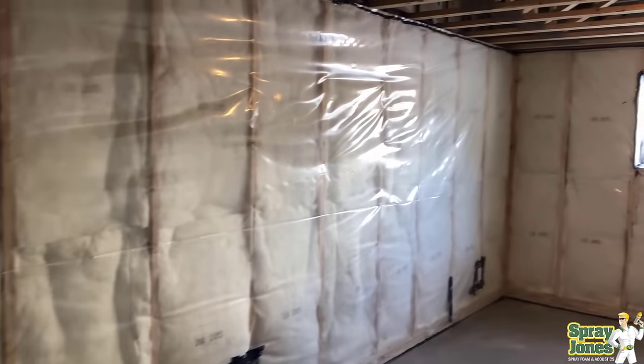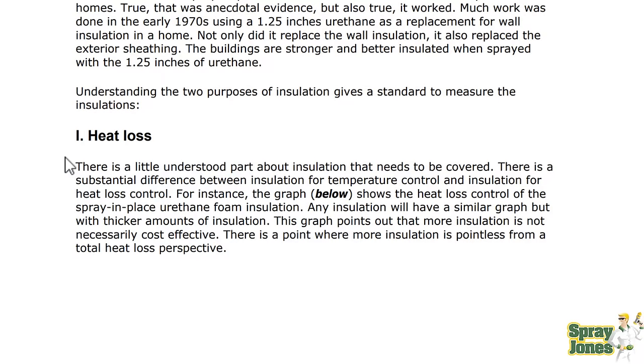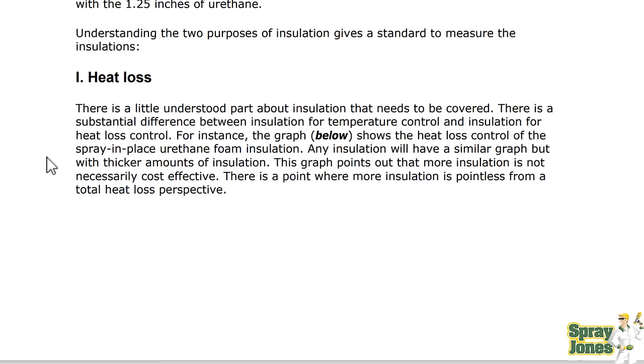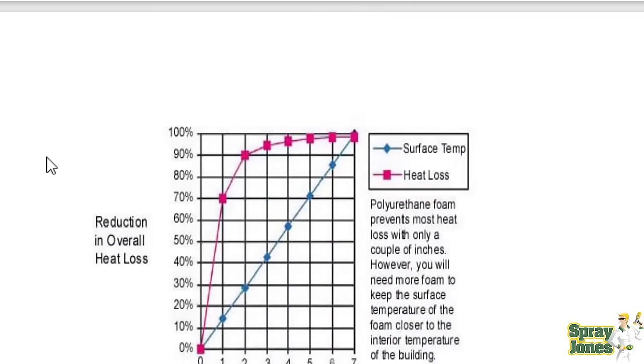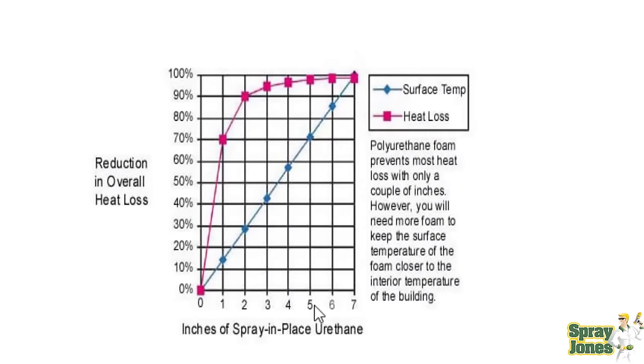There is a substantial difference between insulation for temperature control and insulation for heat loss. The graph shows the heat loss control of spray-in-place urethane foam insulation. More insulation is not necessarily cost-effective — there's a point where more insulation is pointless from a total heat loss perspective. Looking at 1 inch, 2 inch, 3, 4, 5 inches: the surface temperature inside is rising and heat loss has flattened out just over the 2-inch mark. So when we get to 3 and 4 inches, every inch after the 3rd is throwing money away because we're not achieving drastic increases in surface temperature.